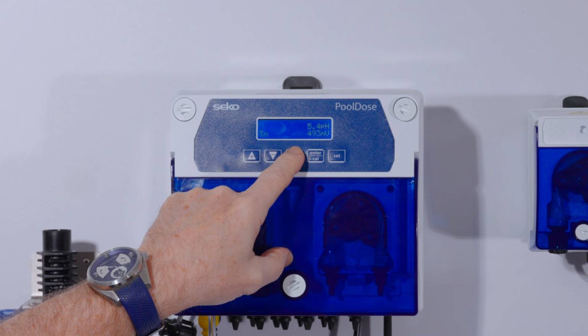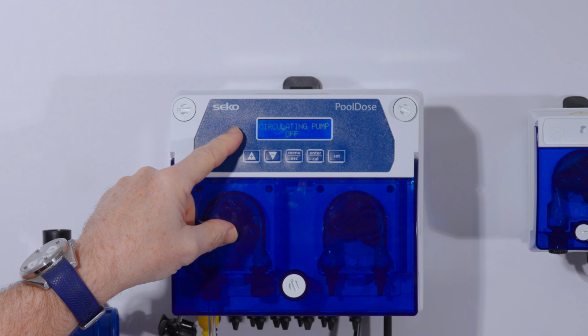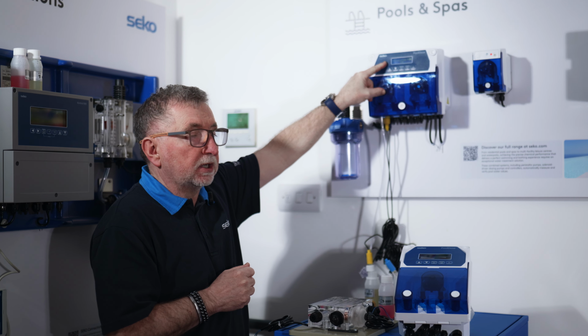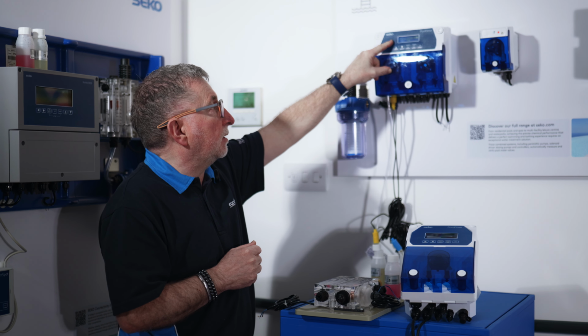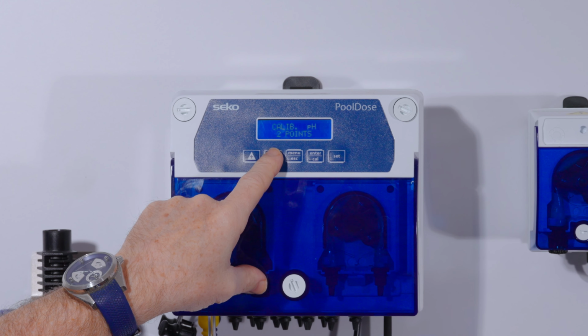The circulating pump. This is a feature to avoid dosing into a static line. The units come with a cable which can be connected directly to the circulation pump, and if the power stops and this function is enabled, it will prevent the dosing. The next one is frequency. This is a totalizer if you use a pulse input from a water meter or flow sensor to give you a calculation on the amount of water that's passed through the system.